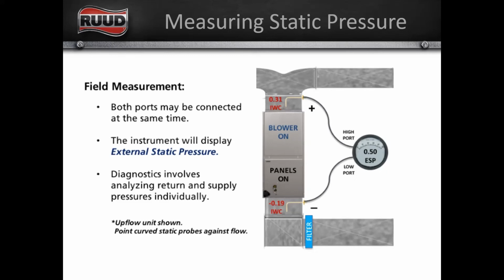On some they might say high, on some they might say low. And what it's doing is calculating, right? We've got a positive 0.31 on our supply. We've got a negative 0.19 on our return. And like I said, when you're measuring your total external static pressure, which is your supply and your return combined, just throw away the signs. It doesn't matter, right? You're adding a positive and a negative, or you're really subtracting a negative. Just add the whole numbers together. So 0.31 plus 0.19 gives us a 0.5 static pressure, which is perfect.